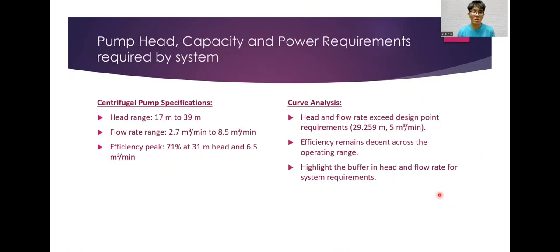Okay, next. The part on pump head, capacity and power required by the system. The centrifugal pump specification that we use has a head range of about 17 meters to 39 meters. The flow range is about 2.7 meter cube per minute to 8.5 meter cube per minute. The efficiency peak is 71% at 31 meters head and 6.5 meter cube per minute. And lastly, the curve analysis that we get is that the head and flow that meet the design point requirement are 29.259 meters and 5 meter cube per minute, and the efficiency remains the same across the operating range. Lastly, we highlight the buffer in head and flow rate for the system requirement.